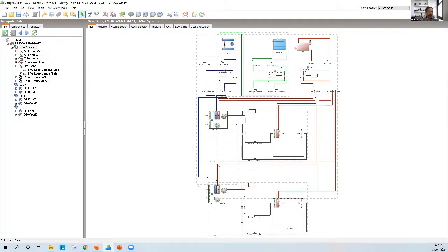as the other AHU. When it needs to do that control will differ, because the east zone will see a higher load in the morning, west zone will see a higher load in the afternoon. But because it's a big floor plate and I've just divided it into two, that difference won't be so much, okay? In reality, you should have a 4-meter wide east zone, a 4-meter wide west zone, a 4-meter wide north zone, and south zone and center zone. Then you can connect different AHUs and controllers together, and then you'll see a big difference in the way they are doing. But for the present, this will do.